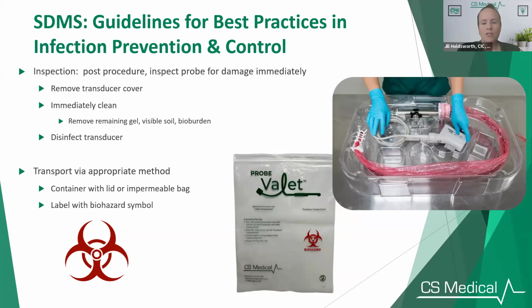We need to make sure that we are transporting per AAMI guidelines, that we have something that's going to separate the two pieces of the probe. The actual probe itself is high level disinfected. The rest of it is low level disinfected. So when you are transporting that soiled probe as well as the clean probe, you cannot let those two sections of the probe touch. Same goes for when you're storing it, which we'll talk about later. But you have to have a method for transporting these probes, TEEs, ultrasound, rectal, all of them, so that the low level and the high level disinfectant pieces do not come in contact with each other, because it is a completely different type of disinfection that's occurring.